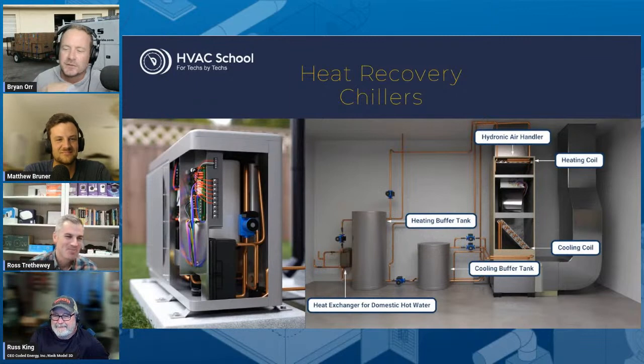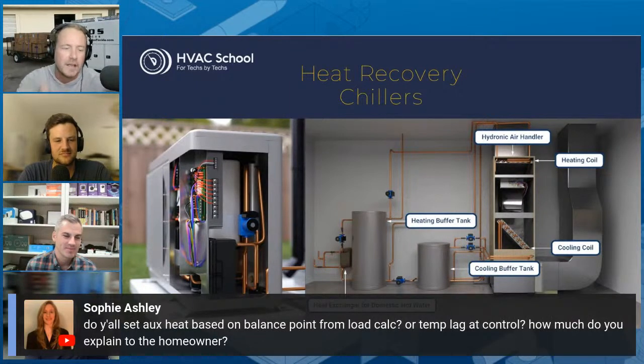Good stuff. I wanted to finish with Sophie. I'm a big fan of Sophie. So she said, do you all set auxiliary heat based on balance point from the load calc or temp lag at control? How much do you explain to the homeowner? So I'll start with my take on this, which is we can get really complicated, but the reality is that when temperature starts to slip, the homeowner gets unhappy. And so allowing the thermostat to largely do what it does with just setting some very practical outdoor temperature limits. We don't have to get down to the exact number, but really all you're preventing is when the homeowner does the smash it up, smash it down, trying to do some sort of setback strategy.